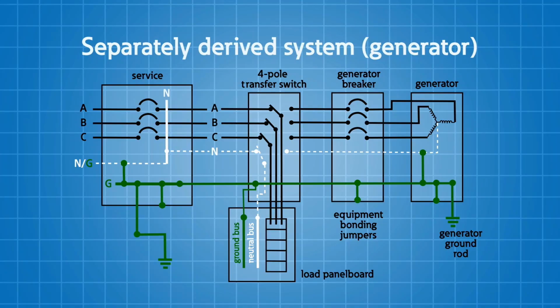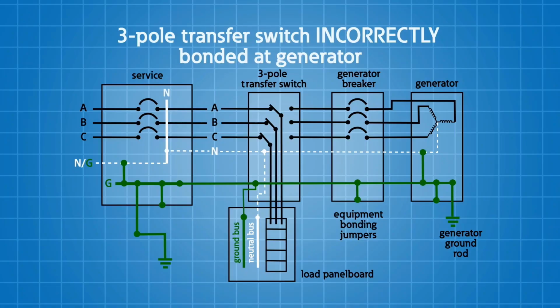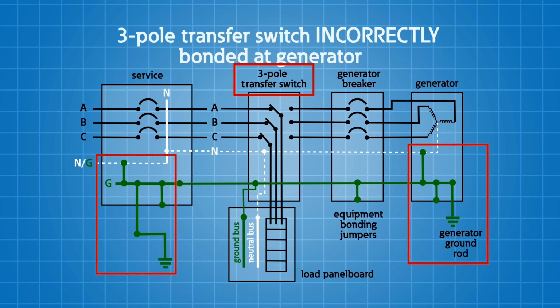Now, why is it important to understand that action will create a separately derived system? Because it will drive what you do in the transfer switch. If you bond that neutral to ground in the generator and you establish a separately derived system, you're going to need to switch the neutral in the transfer switch. That would mean you need a 4-pole transfer switch instead of a 3-pole transfer switch. And if you're bonded in the generator and you're not switching the neutral, you have two separate areas where that neutral conductor is being bonded and you could have circulating currents.